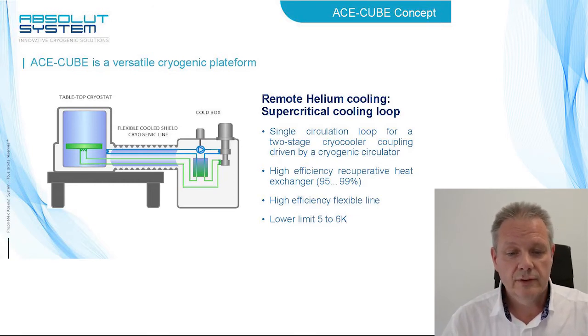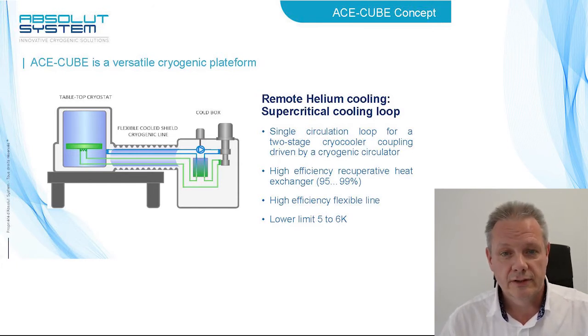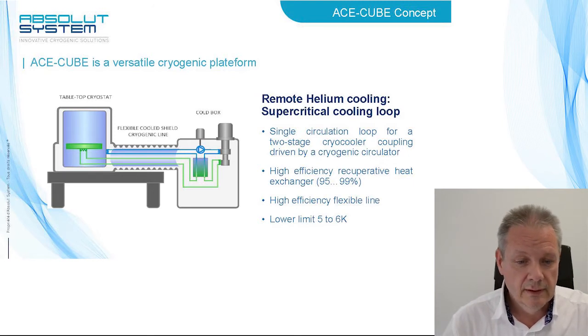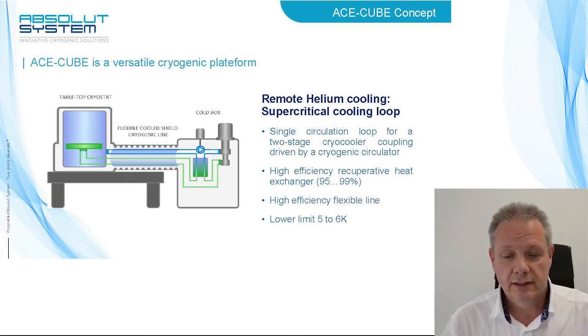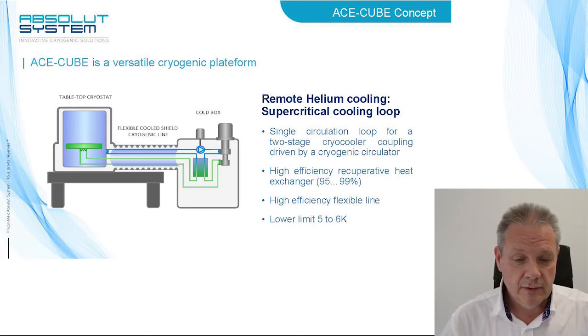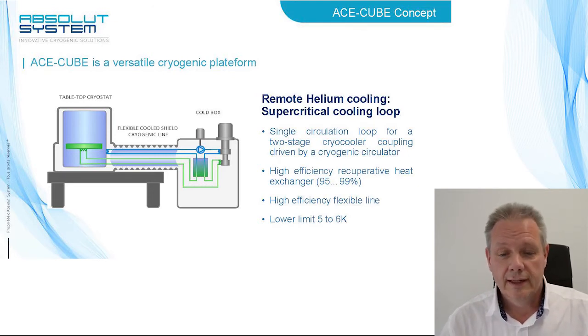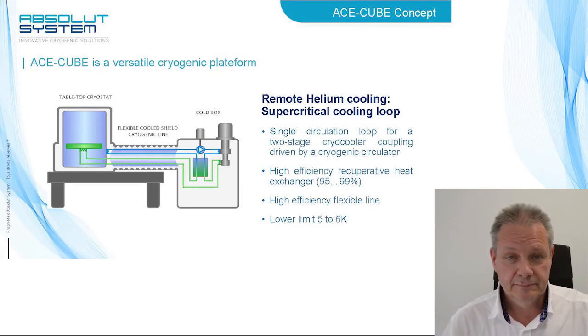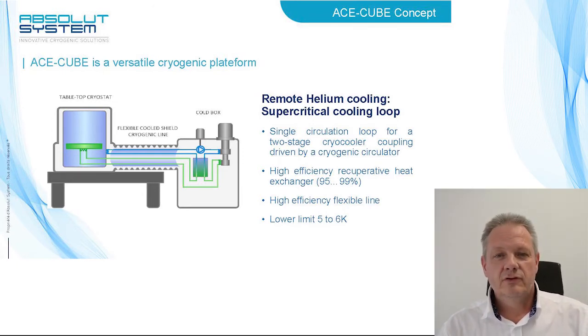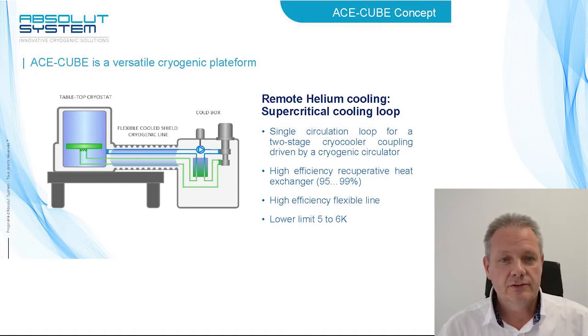By mastering the components, Absolut System can provide a cryogenic solution that meets your application requirements. This vibration-free solution can be totally customized depending on the requirements: experimental volume, cryogenic power, and low temperature. Absolut System has developed several helium cooling loops configurations depending on the final application to meet these different requirements for infrared detectors cooling, where the vibrations are an issue.